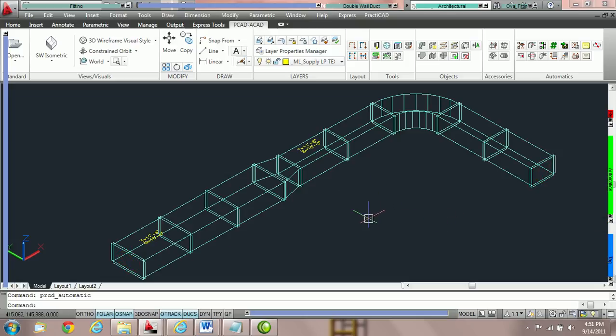The first change we're going to make is an elevation change. To change the elevation of a duct line, or to move it up a specific amount as a whole, other than using the AutoCAD move commands, we can just simply click on the first fitting we'd like to change and then change the elevation of that fitting. If we move that fitting up 2 feet and all of the other ducts are attached, the entire system will move up 2 foot. We do not need to highlight all of the ducts, just the first one on the change.